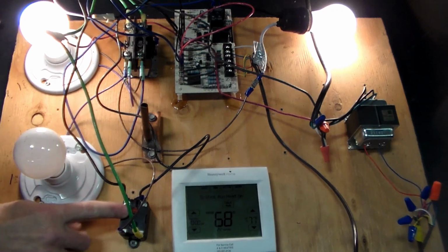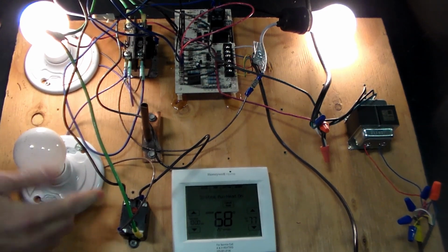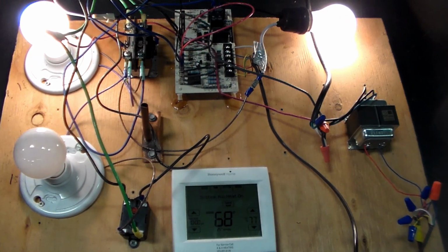And right now I just have my reversing valve set up as a little 24 volt relay because, as we know, light bulbs are not 24 volts, right? So that's the gist of it. Let's start with heat mode. In heat mode, it's going to run like a typical air conditioner would run in the summertime. It's just going to energize the contactor and nothing else. So the compressor is going to come on, the condenser fan is going to come on, but the reversing valve is default in heat mode. So when it comes on, it's going to come on in heat mode.